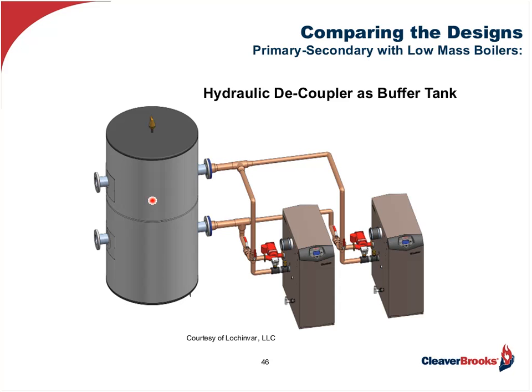The idea for the buffer tank is to provide about 10 minutes of runtime for one boiler at low fire, because you don't want the boilers to cycle. Now, speaking from experience, I've been in boiler rooms where they didn't have buffer tanks, and you would see boilers that had 12 to 15,000 starts in the first year of operation. And we talked about reliability. That's going to shorten the reliability by airing out your burner, putting extra stress on the heat exchanger. So that's why we want that buffer tank in there, so the boilers don't cycle excessively.